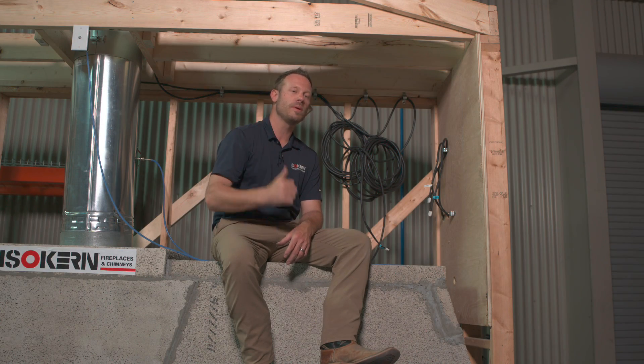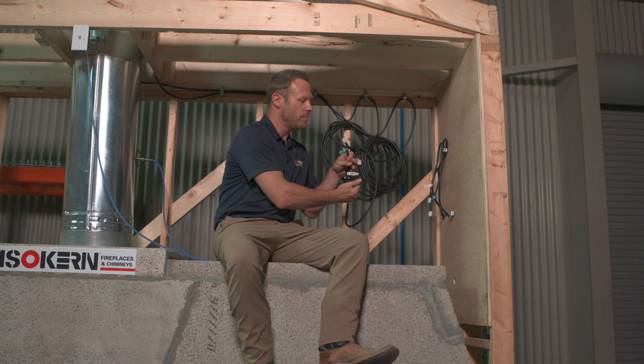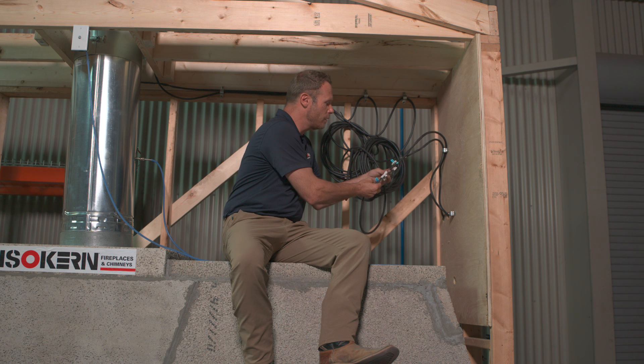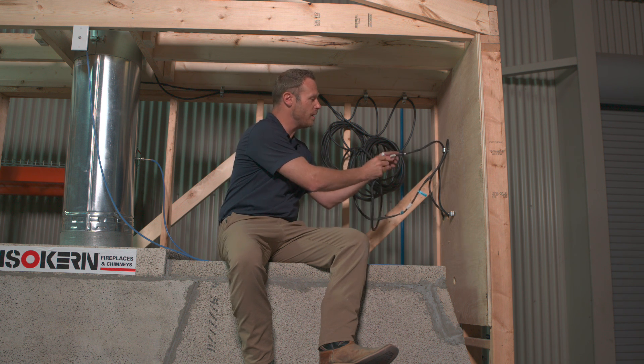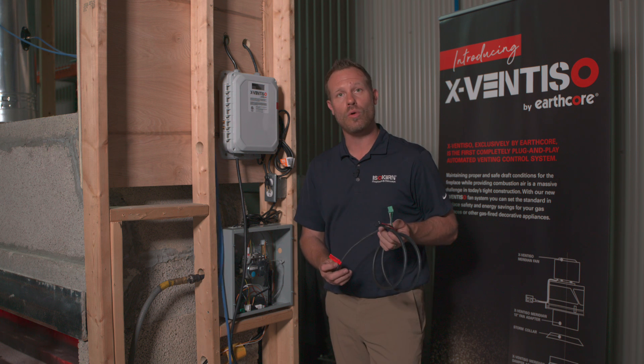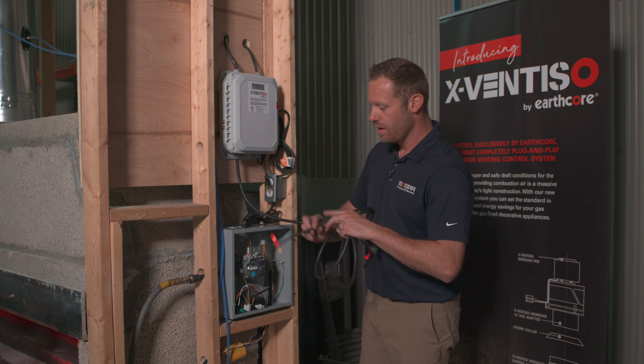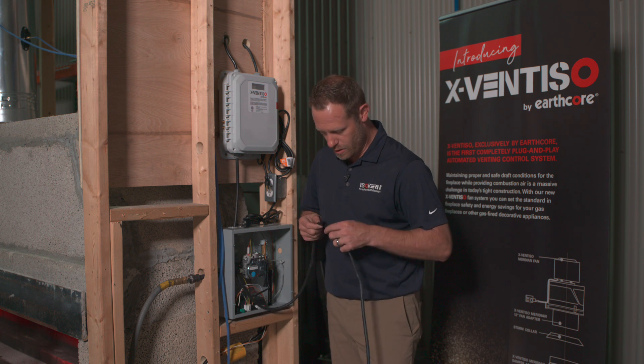Now that we have the fan and damper hooked up, it's time to hook up the wiring. This is where the magic of the X-VENTISO ease of installation comes in. These wiring harnesses are not only color-coded, but they're individual for each component. The damper is blue and has a four-prong connection that only connects with the damper port on the X-VENTISO box. Coming off the X-VENTISO box for the fan is another connection with three connectors that hooks up just as easily. The last connections we need to make are from the draft probes in the room and the stack, and the last wiring harness labeled 'control,' which connects the X-VENTISO control board to the E-VKN control board.